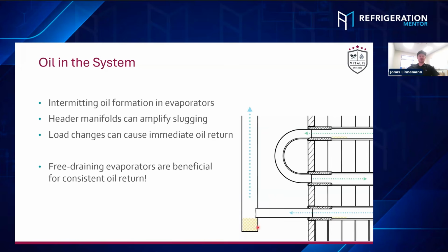So this one shows a not free draining evaporator, but typically evaporators used are free draining. That means that the suction outlet is always at the bottom of the header manifolds of those evaporators. But nevertheless, there is some sort of, let's say, pulsation of oil return, or basically just load changes. As soon as the load increases of those evaporators, it will start to inject more through the expansion valve, and then some oil, which is trapped inside the evaporators, comes back right away and forms or initiates the oil slugs in the system. And so I've seen this before, even in the field in HFC.